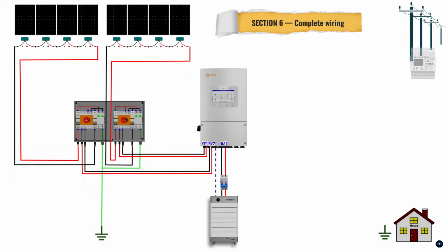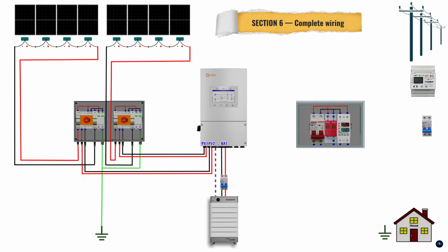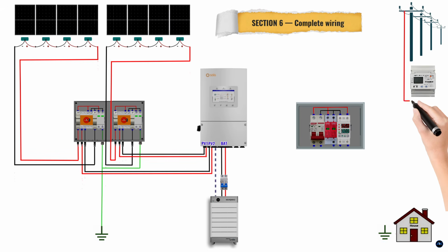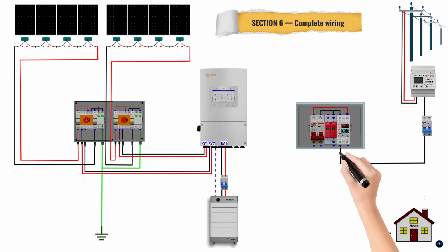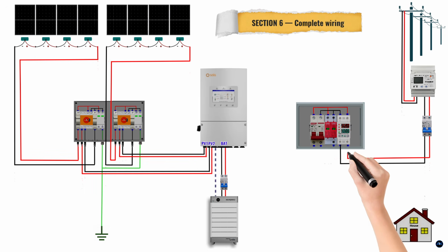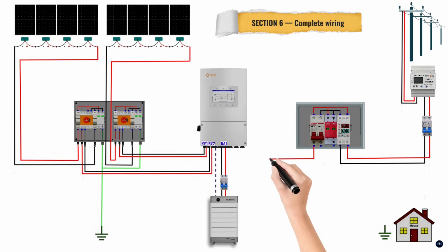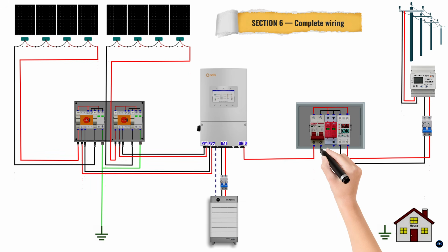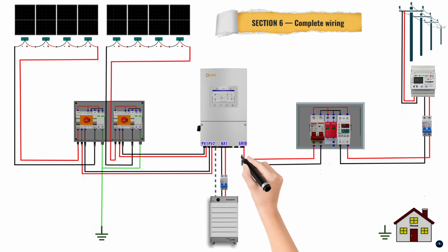Step 3. Grid input. Energy enters through a protection chain in this exact sequence. Energy meter with CT clamp to measure import and export in real time. Then the double-pole AC isolator for safe disconnection. Then the under-over voltage relay, set to trip below 185 volts and above 253 volts. Then the Type 2 AC surge protection device. Then the 40 amp main MCB. From that MCB output, 10mm squared cable connects to the inverter's grid terminals, live, neutral, earth, under 3 meters. Grid isolator stays open.